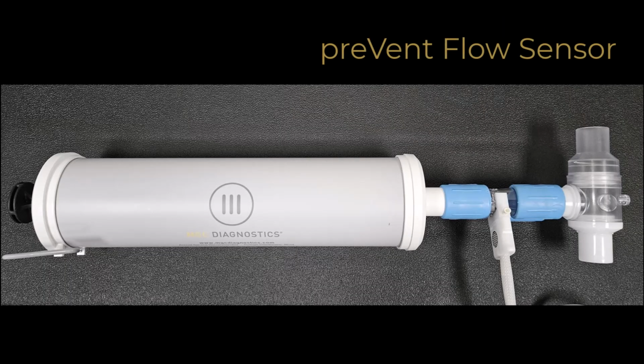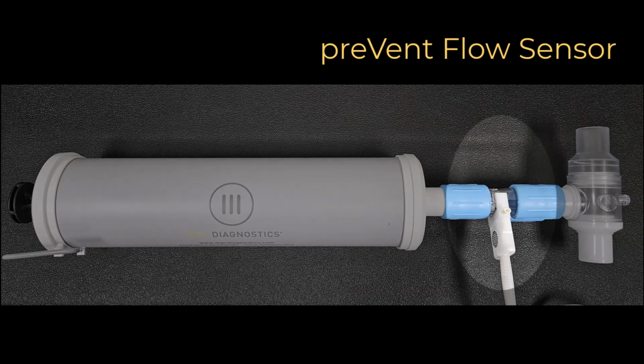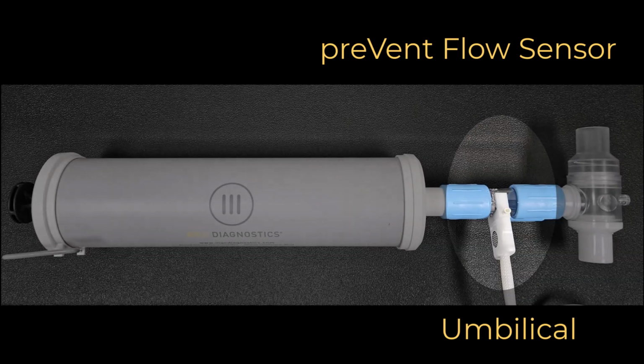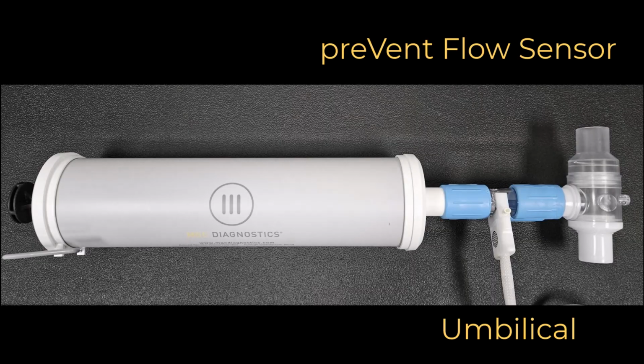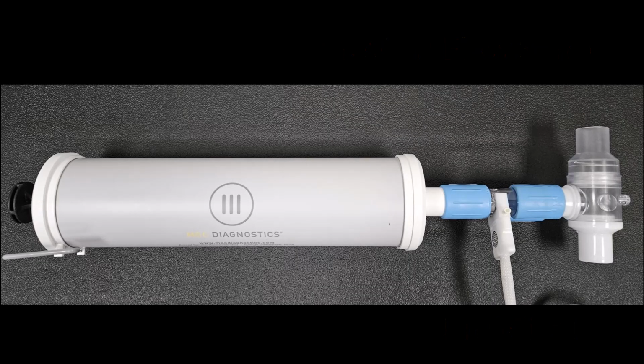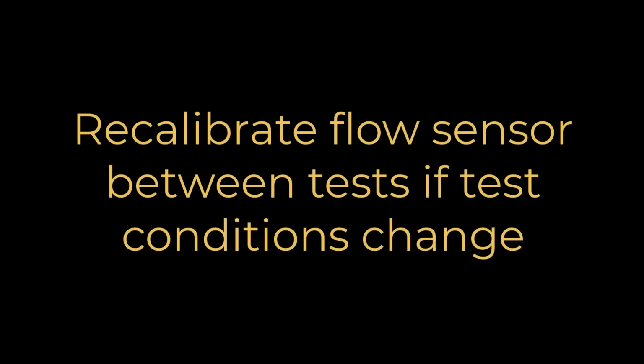In between the two rubber couplers is the preVent flow sensor. The screen side of the flow sensor should be facing the syringe. Attach the umbilical to the flow sensor, and then attach this assembly to the 3-liter calibration syringe. Go to the flow calibration screen of your software and perform a flow sensor calibration. Note, if the next test following the elevated FiO2 test will be on room air, the flow sensor will have to be recalibrated without the valve before proceeding with the room air test.